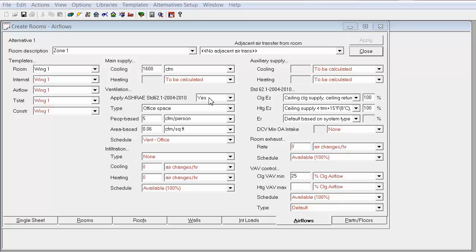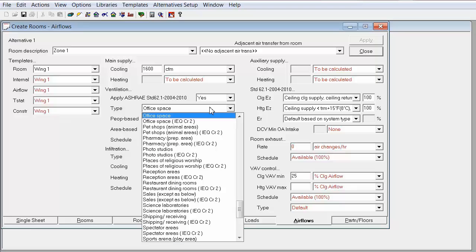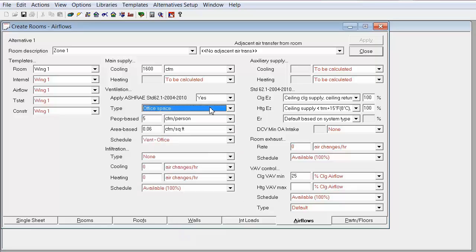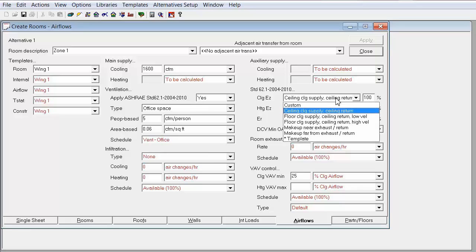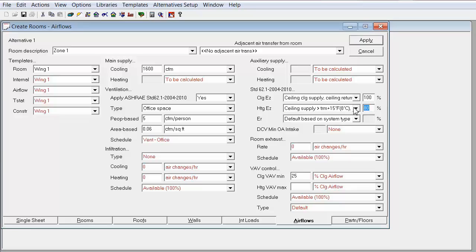Looking at TRACE, the 62.1 ventilation air flows are calculated for each zone when the Apply ASHRAE Standard 62.1 field is set to Yes on the Create Rooms Air Flows tab. The outdoor air flow rate required per person and per unit area for each space type listed in the type field is determined from Table 6-1. These values vary based on the space type. The zone outdoor air flow calculation also accounts for the zone air distribution effectiveness found in Table 6-2, entered in the Cooling and Heating E sub Z fields.